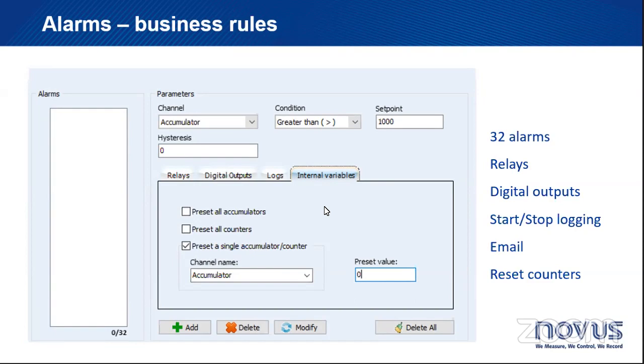So in the example before, where we were seeing counting logic for a flow meter, remember that we are counting to infinity. We are always counting. At some point, we need to reset that counter by some logic. That could be when it reaches a certain limit, or when I press a button, or it could be time-based. Those are all possibilities to use alarms. Alarms can also start and stop logging, and command all the 8 digital outputs that we have spoken about before.